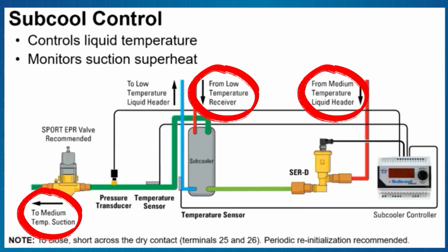So that means this refrigerant flowing through here comes from a different rack than this refrigerant that flows through here. Same gas, just different compressors. They have to be the same gas type, and the only reason is in case I have a leak. This is a problem that plagues heat exchangers. If I'm running water through one side and refrigerant through the other, and I have a leak, I'm going to get water on the suction side.